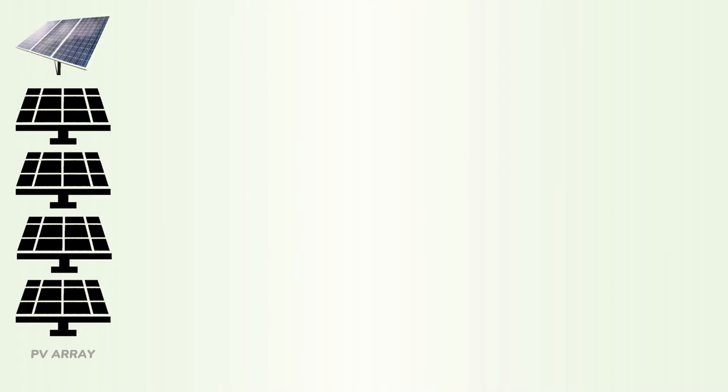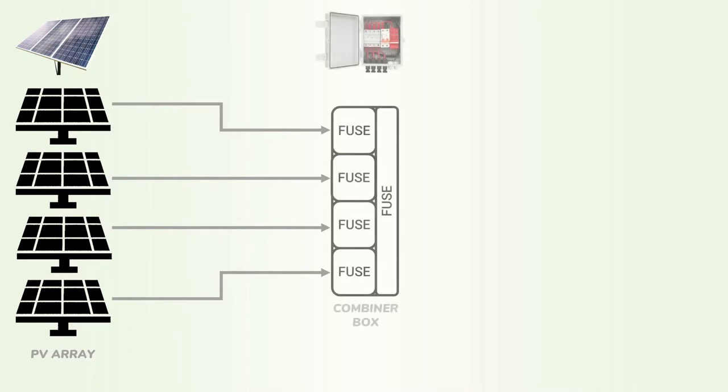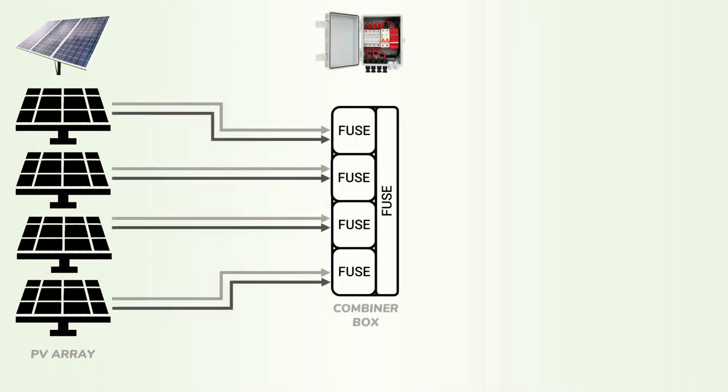Now with either a pass-through box or a combiner box, we can transition from the PV wire or the USE2 wire that's coming from the solar array and then we can transition that into a less expensive wire like the THWN2. So again, in this example, we have four strings in the solar array that will be connected in parallel. In this case, the combiner box serves as a junction for all of the wires coming from the solar array. Now each string in the array has its own set of wires that enter the left side of the combiner box.